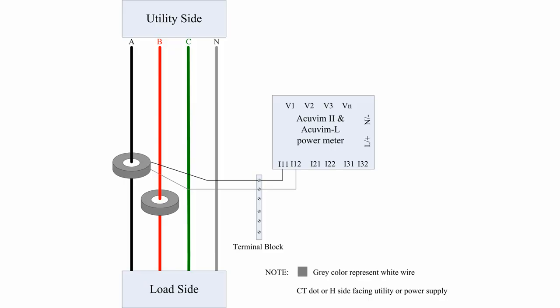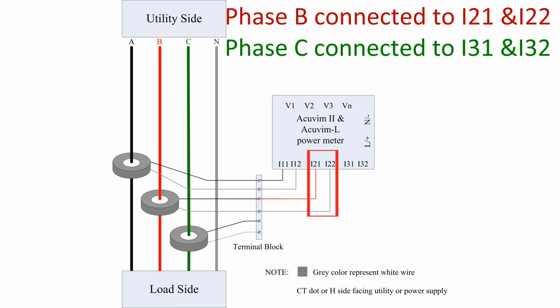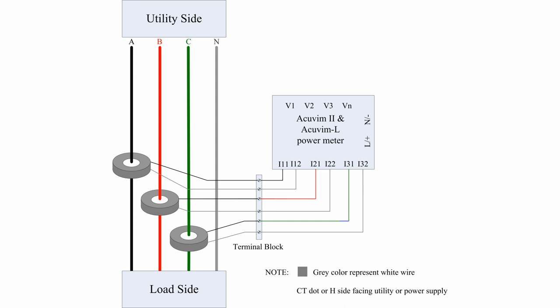Now that we have wired the current input for phase A, the same steps apply to phase B and phase C. Be sure that phase B is connected to I21 and I22, and phase C is connected to I31 and I32 of the current input.